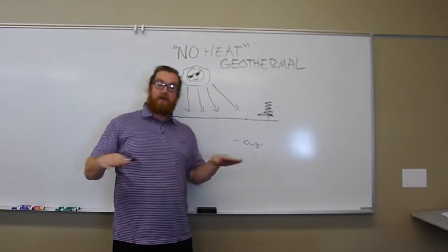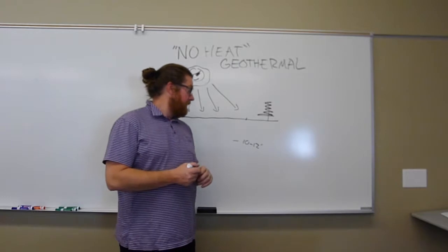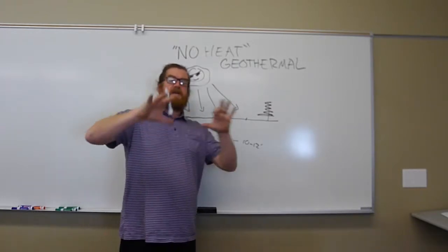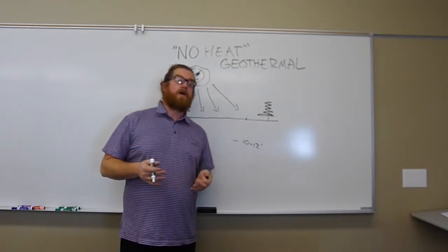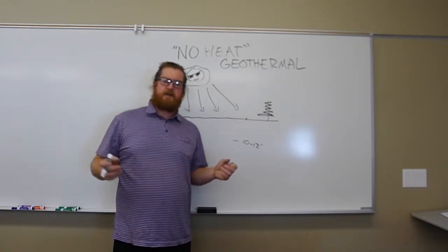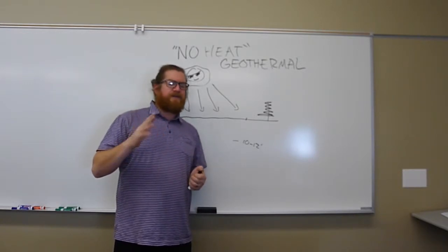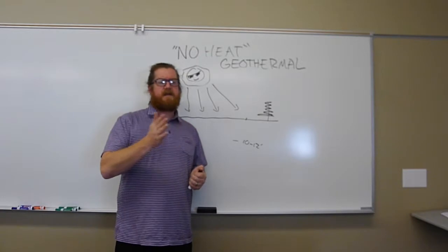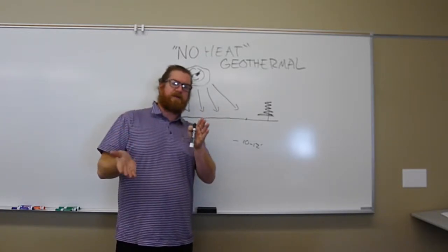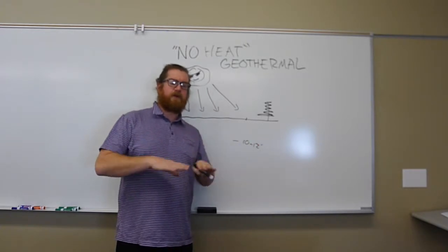And we actually use that to figure out what we call ambient air temperature. Like, what's the average temperature for the area? The ground actually averages it out for us. And when we look at the average ground temperature, and this is also the temperature of groundwater, it doesn't vary very much within the United States. Generally, 53 degrees Fahrenheit to maybe 56. Warmer places have slightly warmer, colder places have slightly colder, but it's all generally in the low 50s. A good average would be to say 54 degrees.